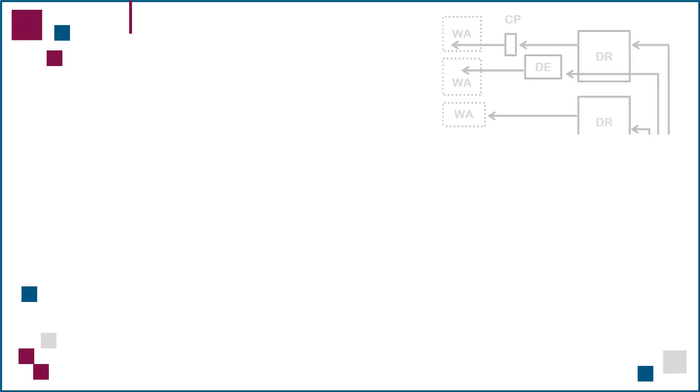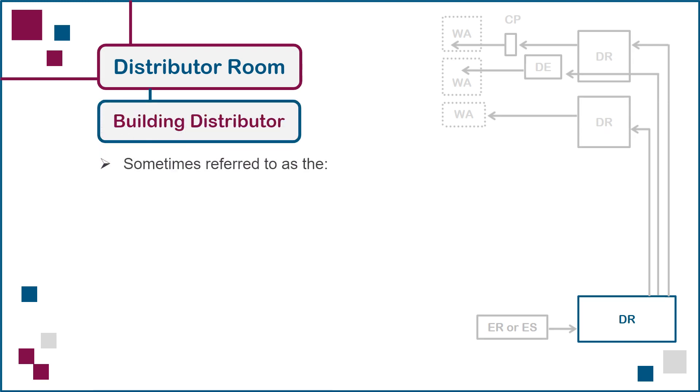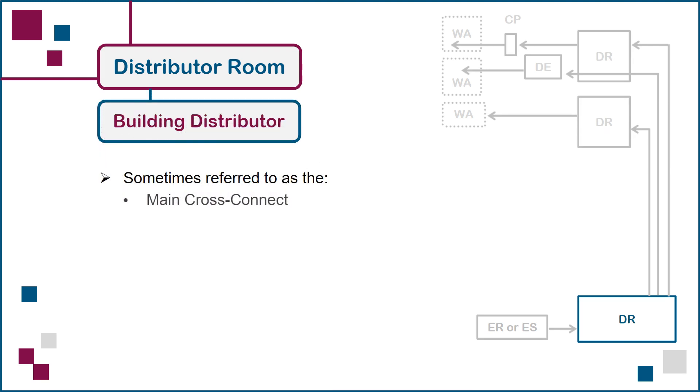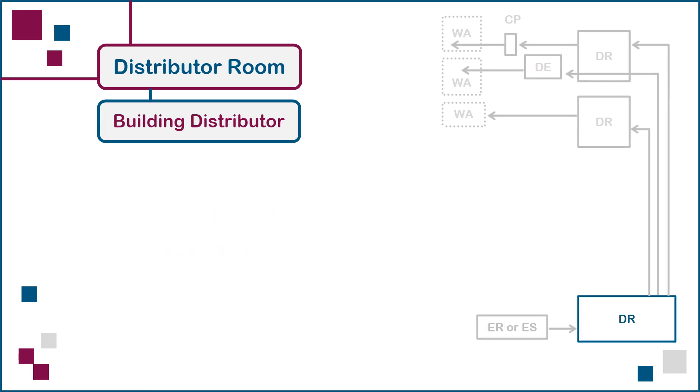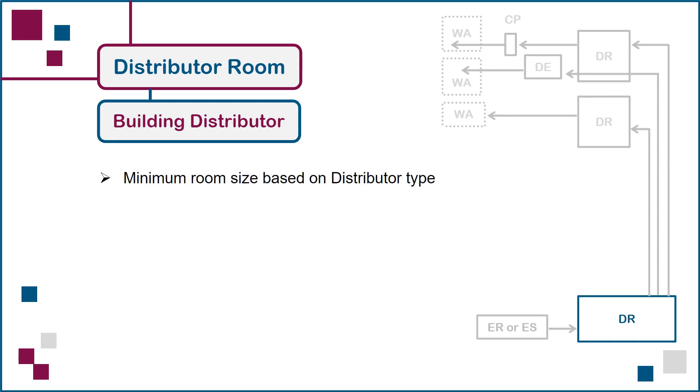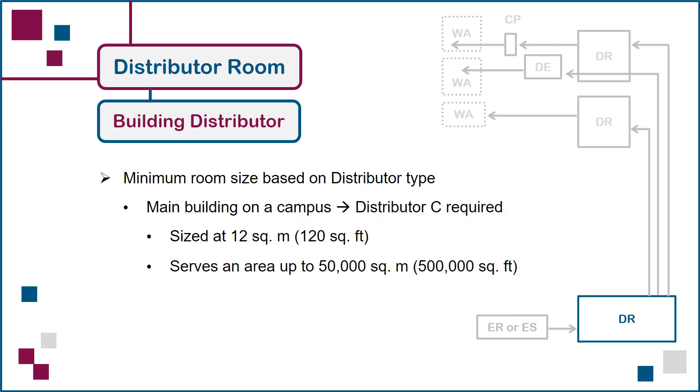Next, we move to the distributor room containing the building distributor, sometimes referred to as the main cross connect or main distribution frame. This room contains network equipment and backbone cabling connections serving the entire building. The distributor room is sized according to the type of distributor it contains. If we're in the main building on a campus, for example, a distributor C would be required, with the room sized at 12 square meters to serve a total of no more than 50,000 square meters.